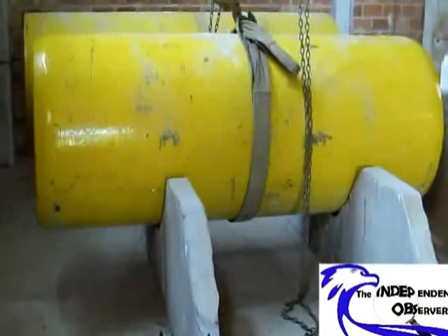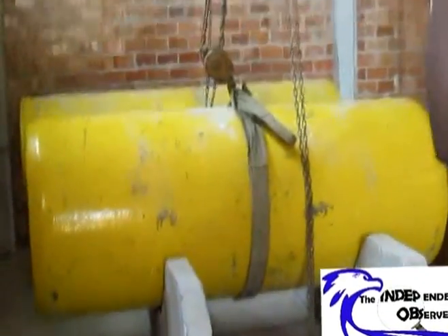So I've already talked about aluminum sulfate. We also add lime periodically, not continuously, while aluminum sulfate is added continuously, depending on how much turbidity is there in the raw water. Then we also have another chemical which is added there, which is chlorine.